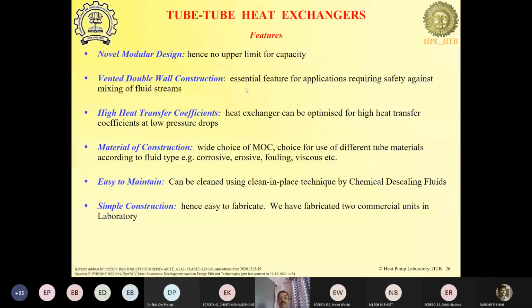And these are vented double walls, so they're essentially safe against mixing of fluids. The high transfer coefficients are ensured because of the unique bends and straight lines intertwined between them. For the material of construction, you can have different tube materials for the different sides, so mixing and matching is possible. So you don't have to go to very fancy materials of construction which are compatible with both the fluids. Just to give you an example, if you have ammonia and seawater, the only common material which is readily available is titanium, but then titanium heat exchangers can be very costly and difficult to manufacture. In our case, we used stainless steel or carbon steel on the ammonia side, and we used cupronickel on the seawater side.